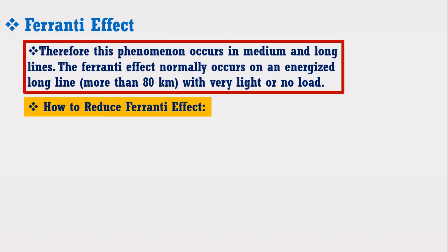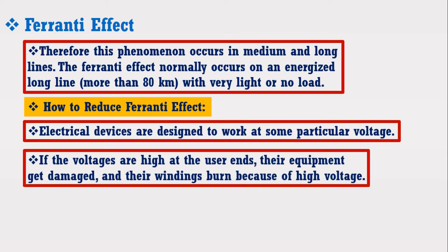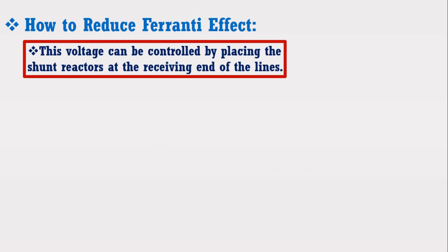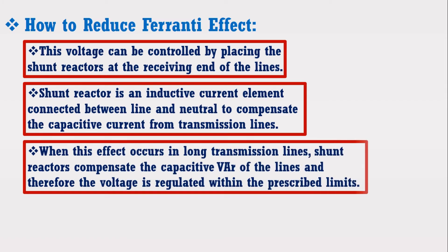Electrical devices are designed to work at some particular voltage. If the voltages are higher at the user ends, their equipment gets damaged and their windings burn because of high voltage. This voltage can be controlled by placing shunt reactors at the receiving end of the lines. A shunt reactor is an inductive current element connected between the line and neutral to compensate the capacitive current from the transmission line. When this effect occurs in long transmission lines, shunt reactors compensate the capacitive VAR of the lines and therefore the voltage is regulated within the prescribed limits.